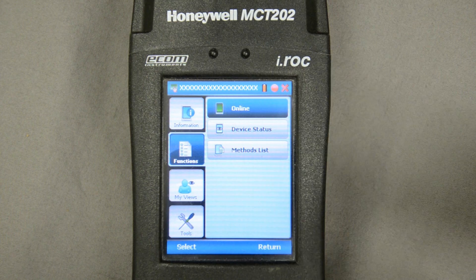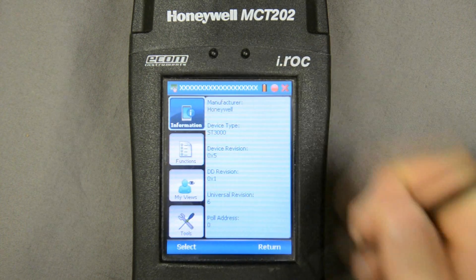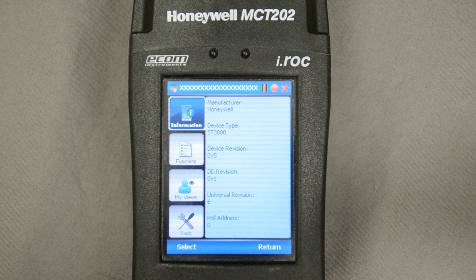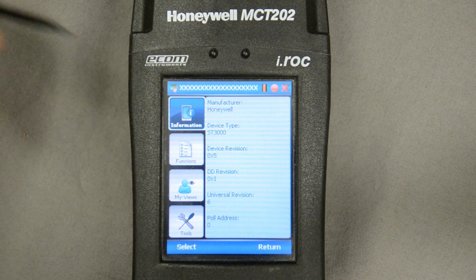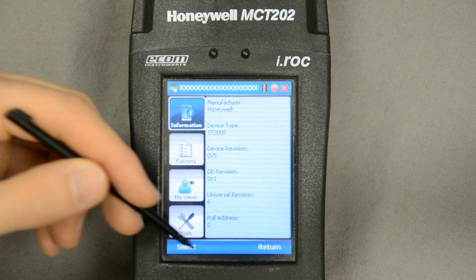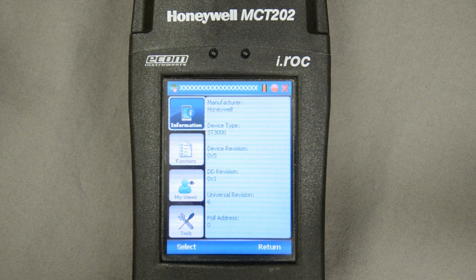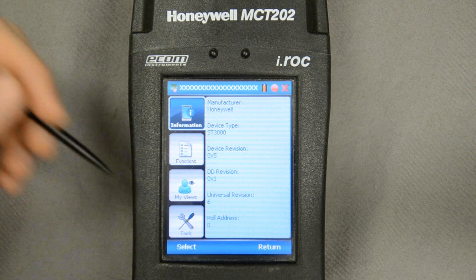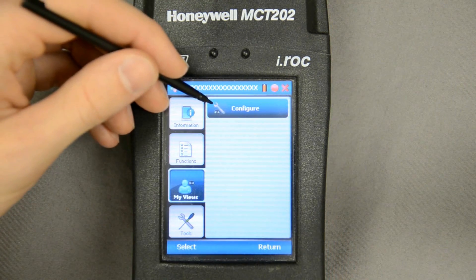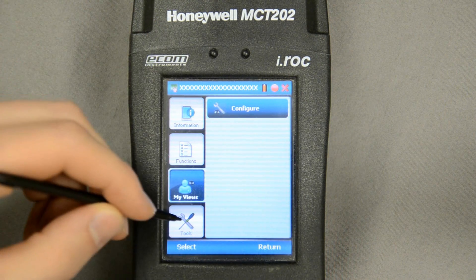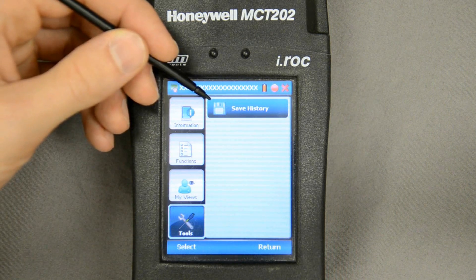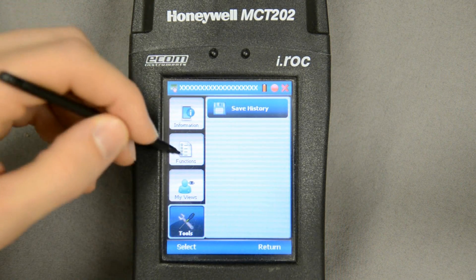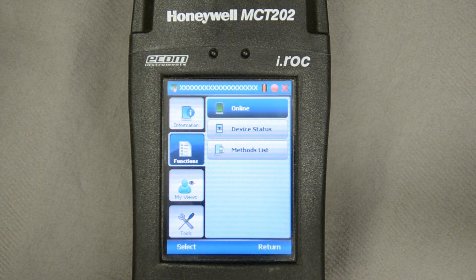In this situation I'm connected to a HART transmitter, in this case a DP transmitter. I've pulled up the program on the MC Toolkit that communicates with HART transmitters and pulled all the information from the device into it. On the information screen you see the specifics of the transmitter, the type, and whether it has a HART address or not. Here I can look at how I want to configure the views on the screen of the MC Toolkit.